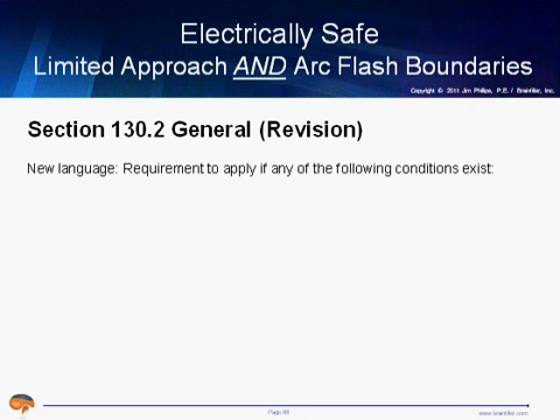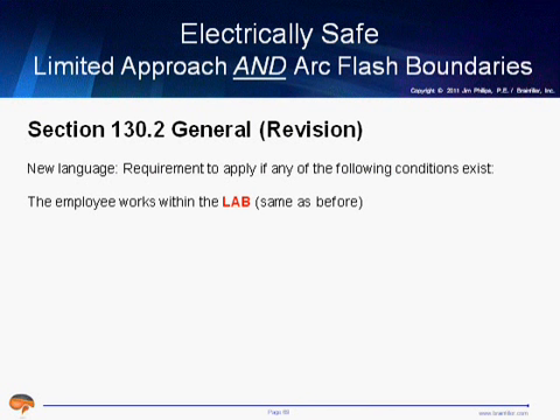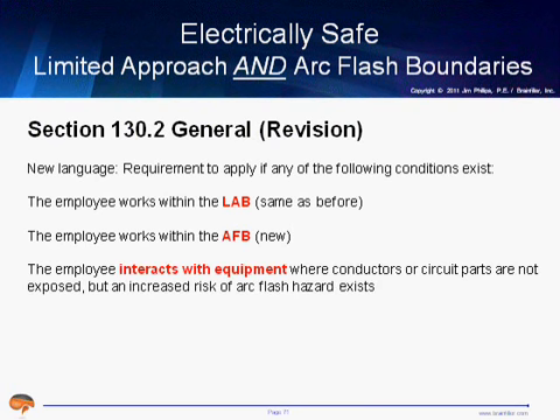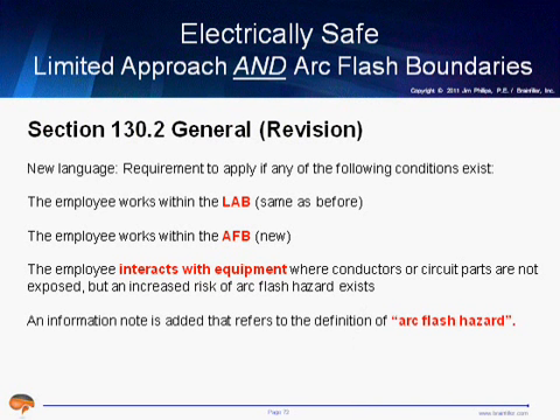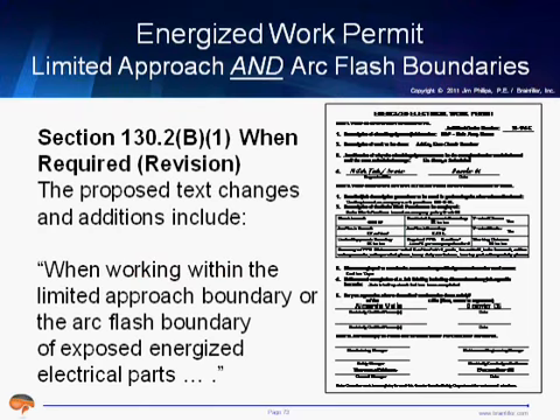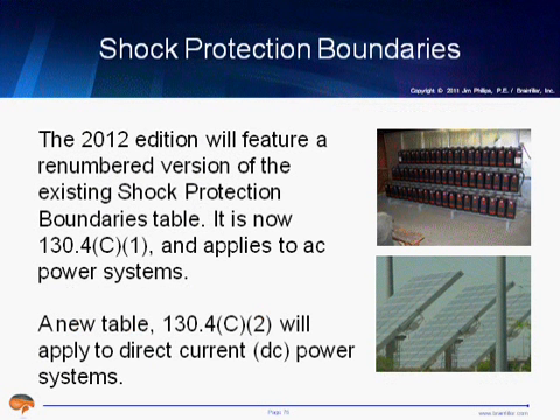The electrically safe working condition, the arc flash boundary has entered into this as well. And with this, it's always been applicable if you're working within the limited approach boundary, but now the arc flash boundary has also been included, and also interaction. In the 2009 edition, there was language about an arc flash hazard could exist if there's interaction with equipment that could possibly create an arc flash hazard. And in fact, this new language in this section refers back to the definition of the arc flash hazard. Energized work permit requirements now also are going to include the term arc flash boundary. That if someone is working within the limited approach boundary or the arc flash boundary, the requirements of the energized work permit are going to come into play.